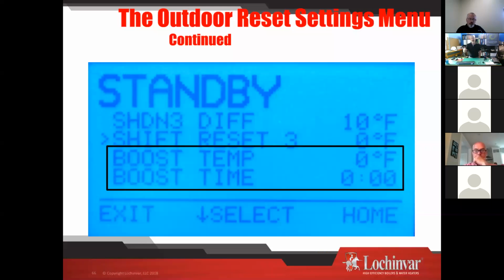And then your boiler's going to say, all right, whatever happened, I'm going to boost the temperatures. Whether it's a power outage, whether they shut the thermostat off, forgot to turn it back on, any of those sort of things. It happens in my house all the time. The weather gets quasi-nice, and by quasi-nice, it's 48 degrees out. My wife decides she's got to have a window and a door open, cranks them open, shuts the thermostat off, and then all of a sudden it's 50 degrees in the house and cranks it on. And because my water temperatures run real cool, my boiler might go a couple of weeks before it would ever get back up to temperature because it's not designed to make that big jump. But that's what that's going to do for you right there. It kind of solves that scenario.